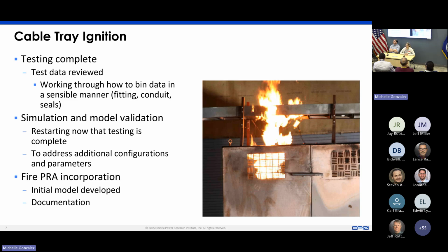Nick talked about the cable tray ignition project. This was one of the areas where the model we have to calculate time to damage leads to results that postulate damage within one or two minutes. So we decided to work with the NRC and NIST to do tests to see how long it would be until ignition was likely to occur. We tested a variety of configurations, including more testing this year to understand how penetration seals and conduit seals would affect fire growth and behavior.